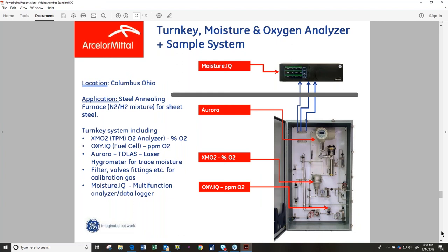So as I mentioned, one of our key applications that we get involved with is in metal processing. And very often we're making three measurements in the atmosphere: moisture through our moisture sensors, oxygen measurements, and hydrogen measurements as well. So there you just see a turnkey panel that's going to draw a sample from the furnace. And that furnace gas is hot, with a lot of particulate in it, so it all has to be cooled and cleaned up. We have an integrated sampling system with, in this case, a lamb's wool lanolin filter to knock out the soot that comes out. And in this case, we're actually using one of our laser hygrometers to measure the moisture. So ArcelorMittal, of course, makes sheet steel.